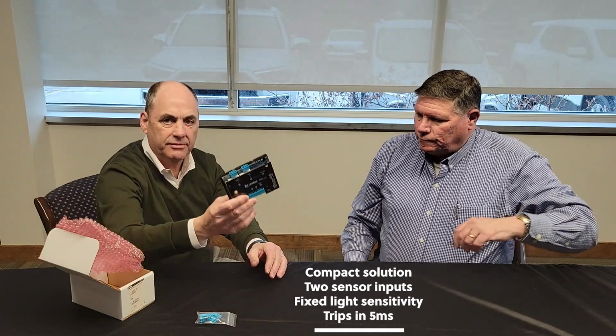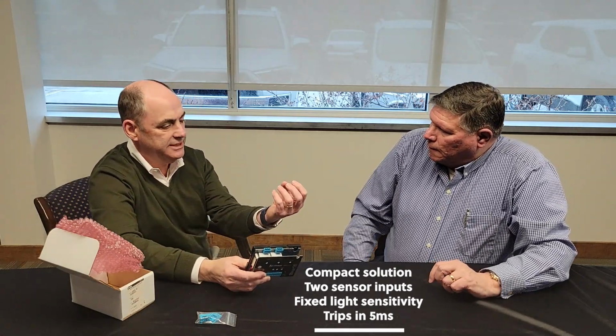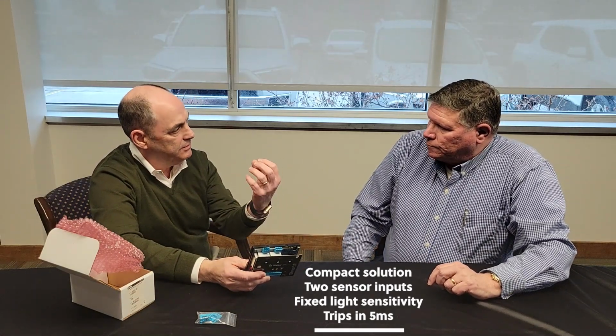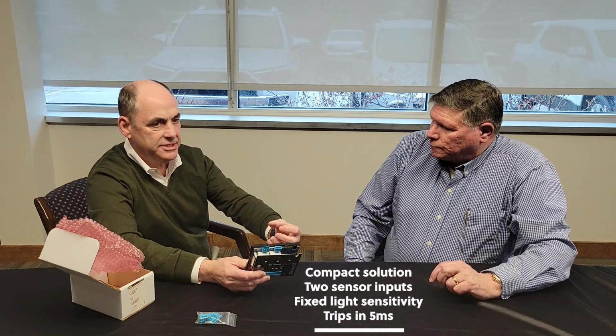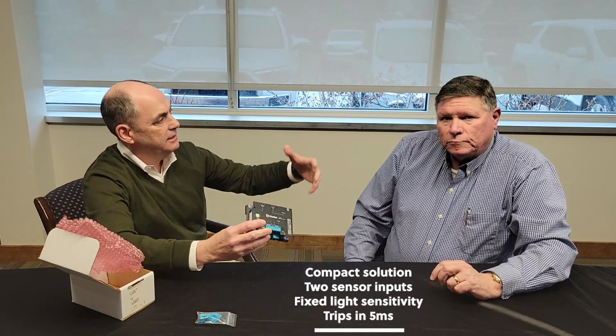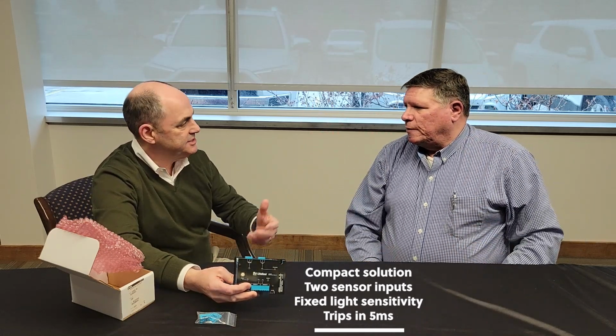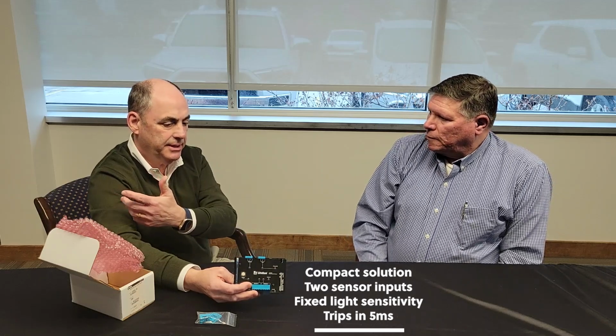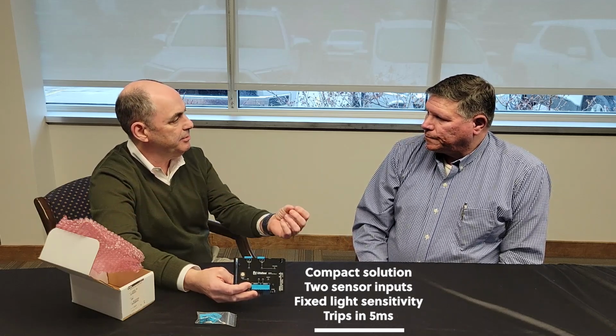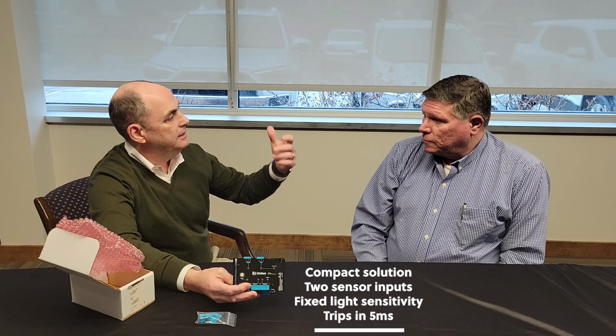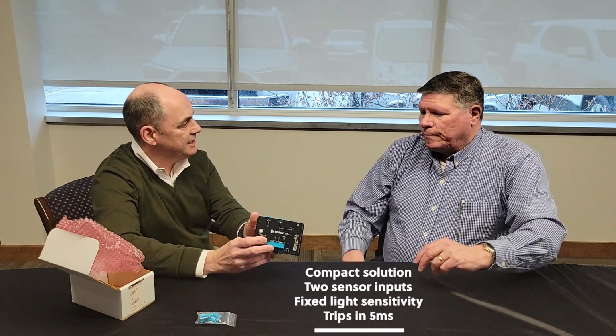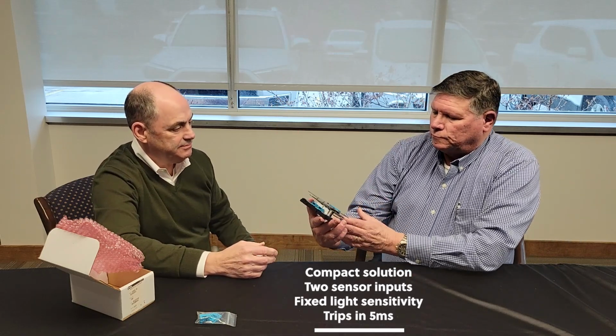Sensor-wise, the way an Arc Flash relay works is you're trying to detect a flash of light, which is the beginning of an Arc Flash incident. The quicker you can pick up that light, and it's within milliseconds. The bigger Arc Flash relays will trip a breaker within a millisecond. Wow. This one's 5 milliseconds, so it's a little bit slower, but it's based upon the application.